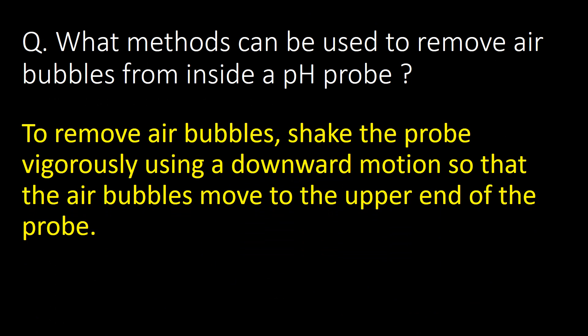What methods can be used to remove air bubbles from inside a pH probe? To remove air bubbles, shake the probe vigorously using a downward motion so that the air bubbles move to the upper end of the probe and can be expelled.